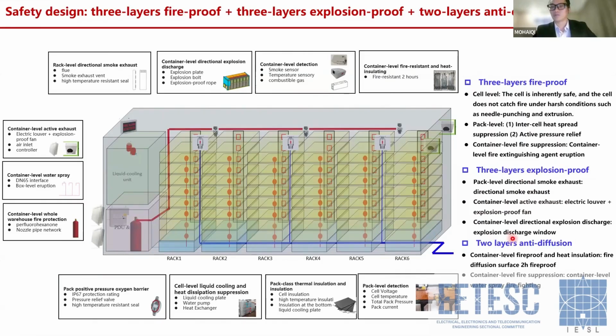And the two layers to anti-diffusion. So container level fireproof and heat insulation, the fire diffusion surface is more than 2 hours fireproof. Why have this kind of requirement? Just imagine after burning, maybe 4 hours, 6 hours, 8 hours, even 10 hours, if you want to move this container, it definitely cannot be used. If you want to move this container somewhere, your system should be stable enough to use a forklift or crane to move it out. Otherwise, if someone is doing the moving work, it will cause a second hazard.